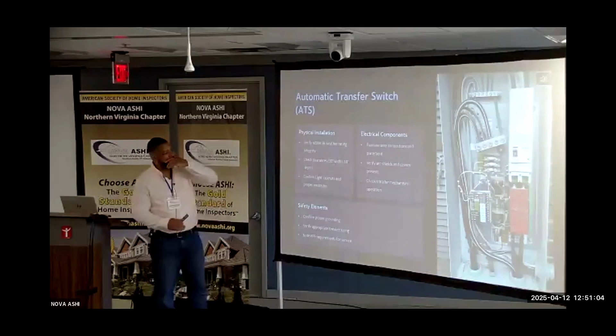So those arc shields are very important, but if you're going to look at the connections behind them, you have to remove them. And the one with the red, you just got to squeeze that little spring there that comes out, and you can look at the connections there as well. So this little black thing here, that's called the transfer mechanism. It actually works off of magnetism as well. You energize the coil and it either goes on or off. And it's an interesting thing.